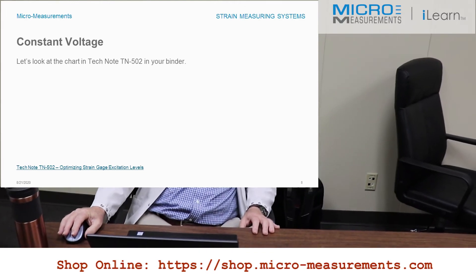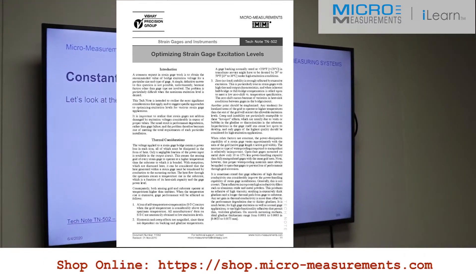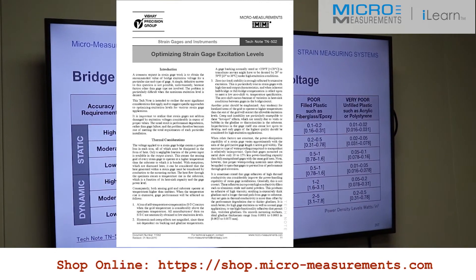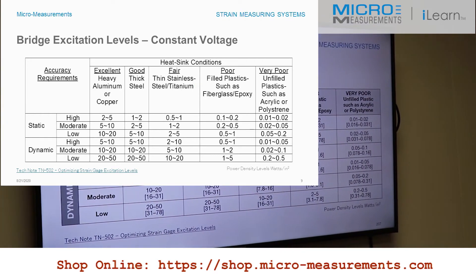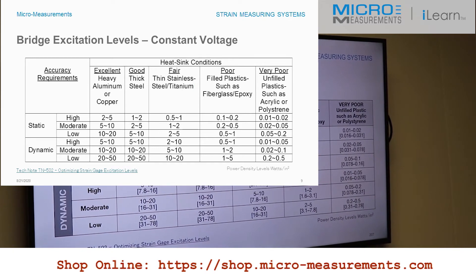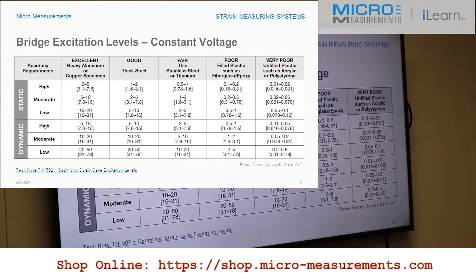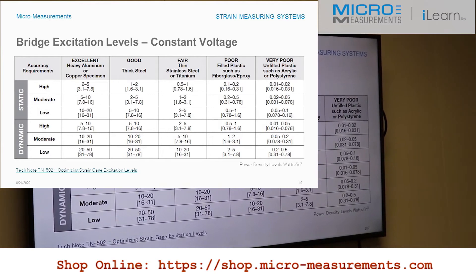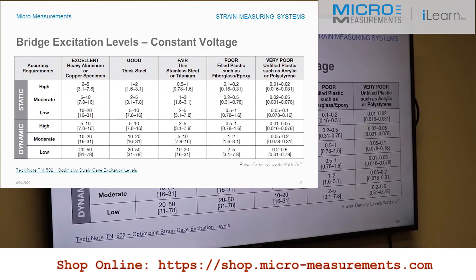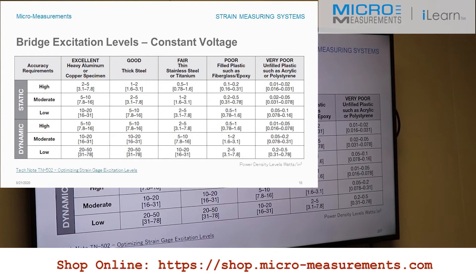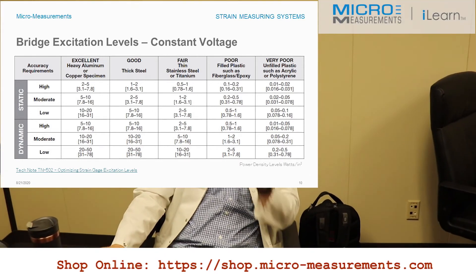We do have tech note 502 that shows you the calculations for predicting what your maximum excitation would be. There are several steps in using this tech note. First, we establish our accuracy requirements. We're going to make a static measurement looking for moderate accuracy, bonded to an excellent heat sink — aluminum — and a very poor heat sink — unfilled plastic. The watts per square inch for moderate accuracy is 5 to 10 watts per square inch, and for plastic it would be 0.02 to 0.05 watts per square inch. Very much different.